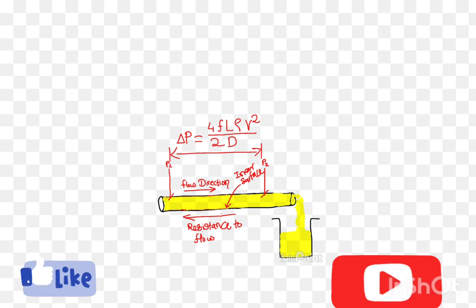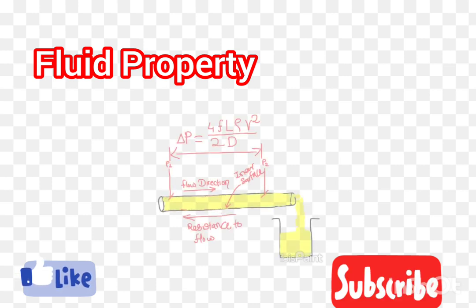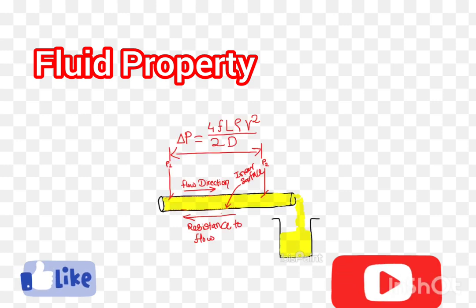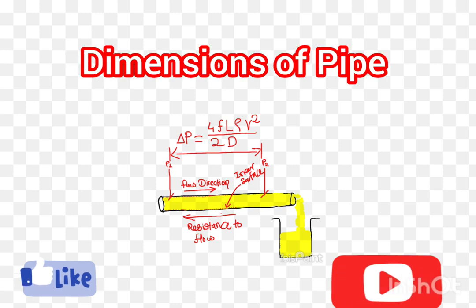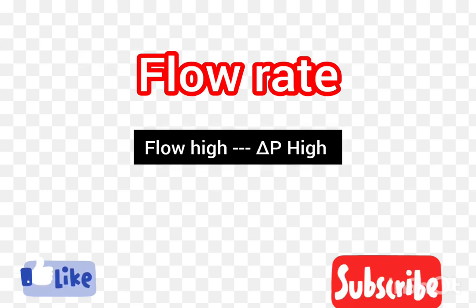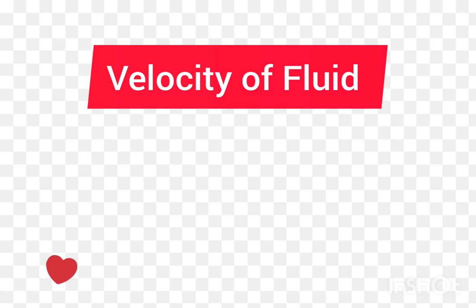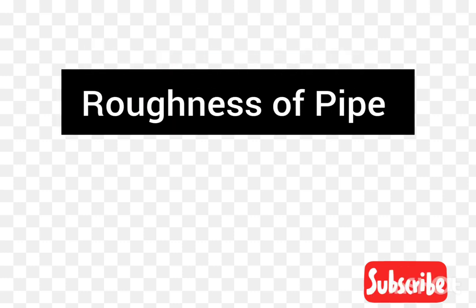To accurately calculate pressure drop due to friction, we need to consider several key factors. First is fluid properties — the dynamic viscosity and density of the fluid affect the level of friction within the pipe. Second is pipe dimensions — the length and diameter determine how much resistance the fluid encounters. Third is flow rate — the velocity of the fluid is a crucial factor; faster flow results in greater friction and more significant pressure drop. Fourth is pipe roughness — the roughness of the pipe's inner surface can significantly impact friction and pressure drop.